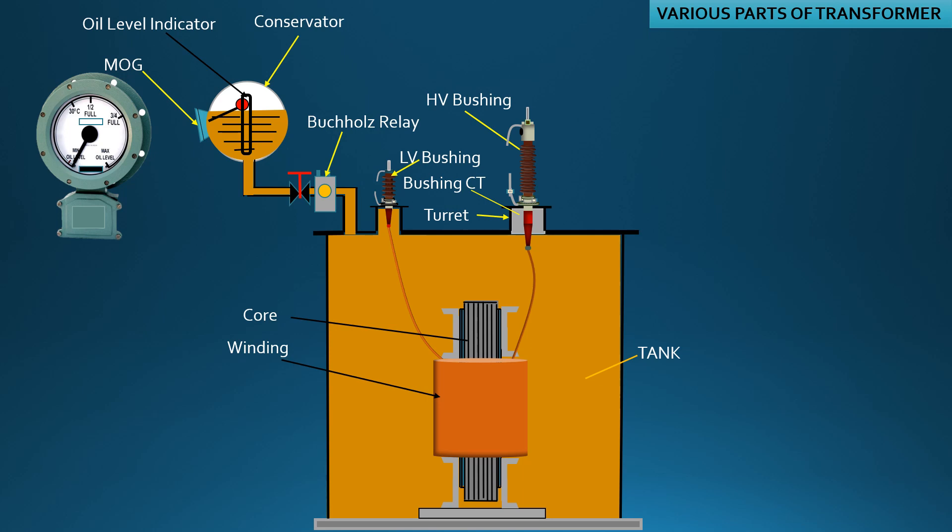MOG indicates the level of oil inside the transformer tank. The conservator tank during normal operation remains one-third filled at 30 degrees Celsius.